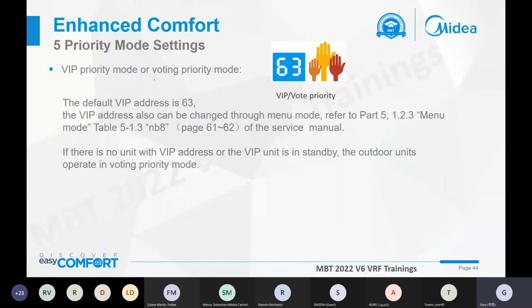For the VIP or the vote priority, the default VIP address is 63. It means that when you set a VIP indoor unit, no matter how many indoor units are in the system and whatever mode the other indoor units want to run, they should all follow the VIP. That means all the indoor units should follow the VIP indoor unit.